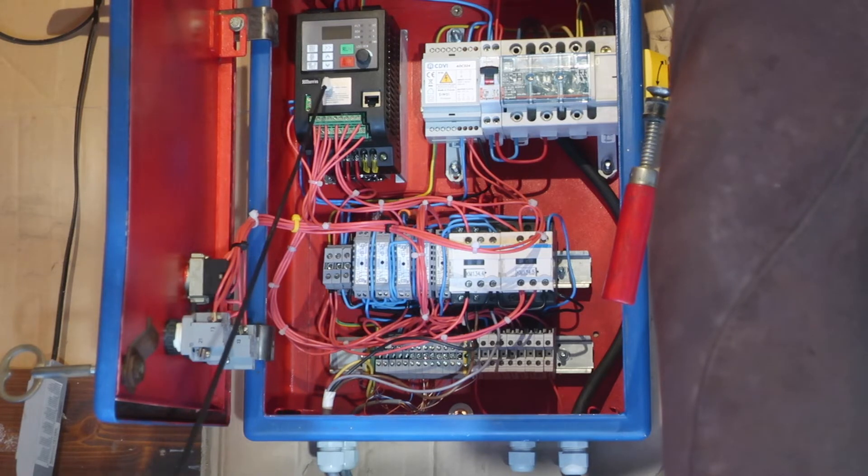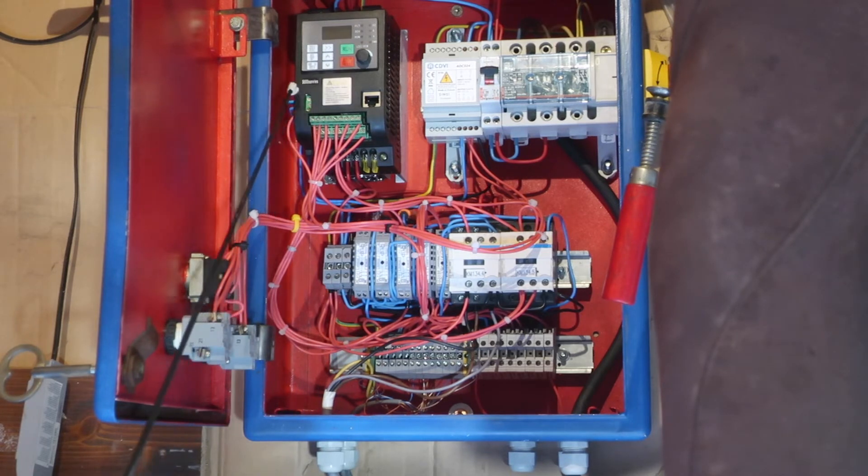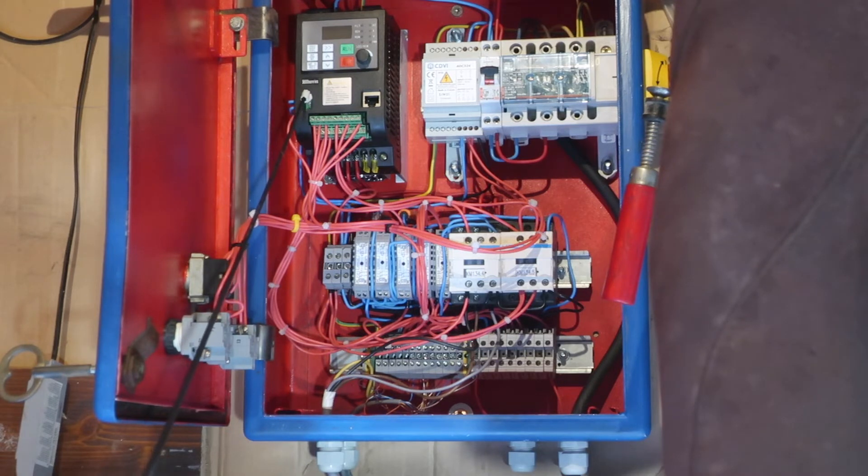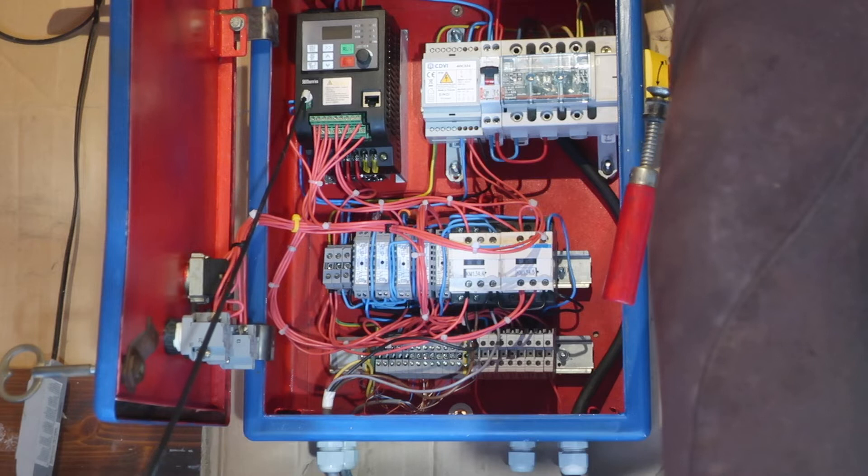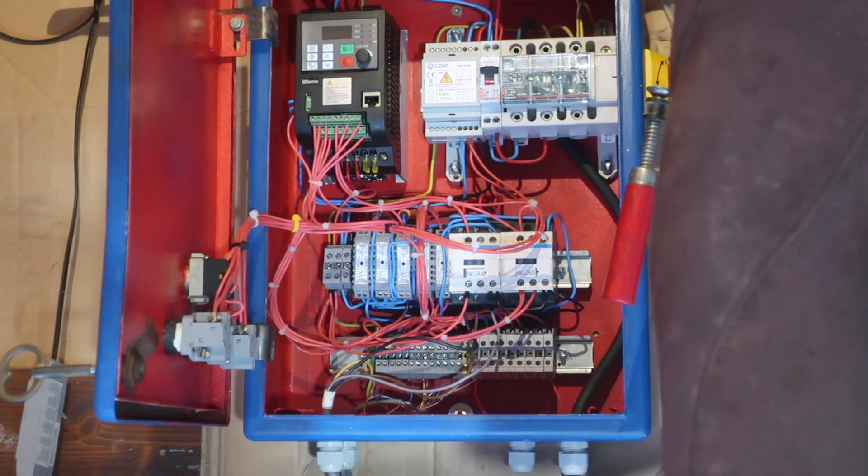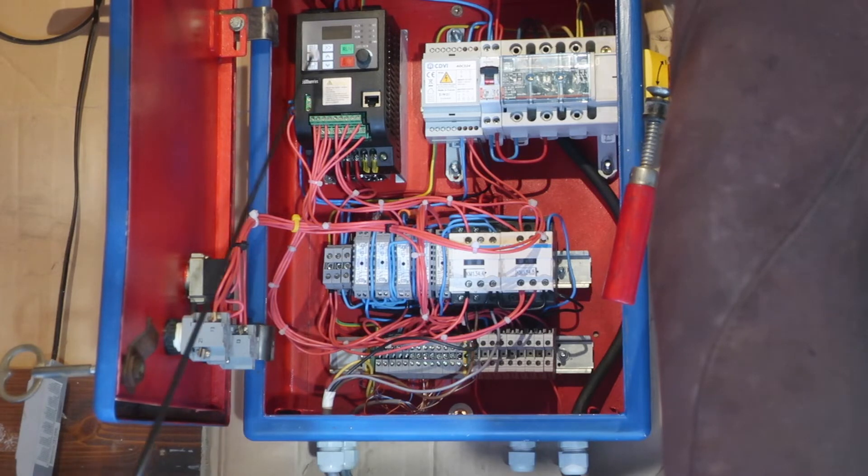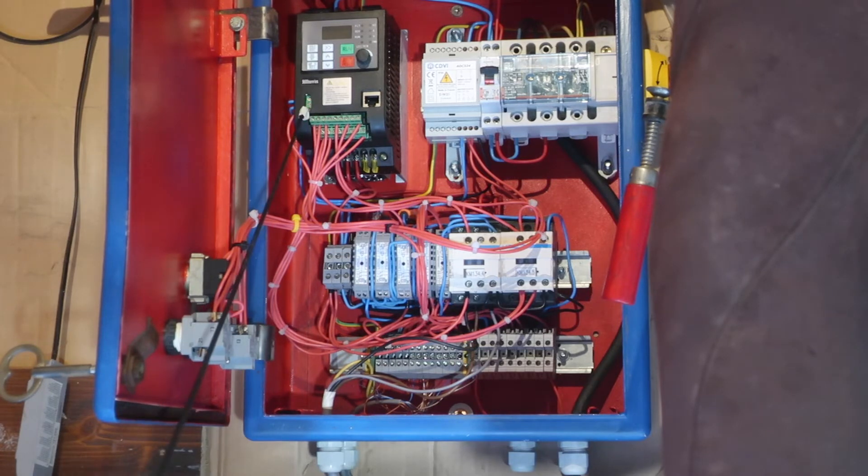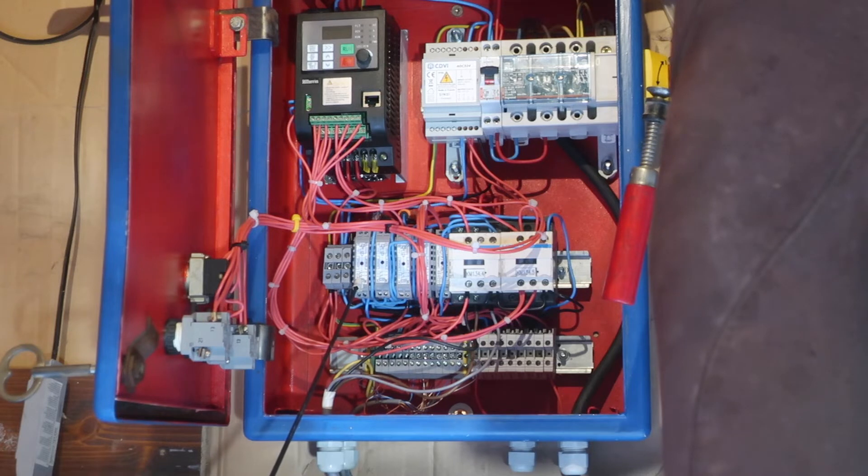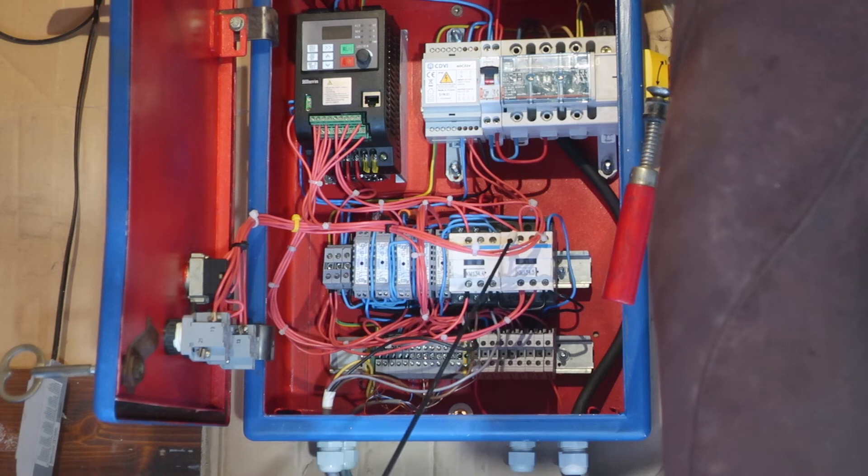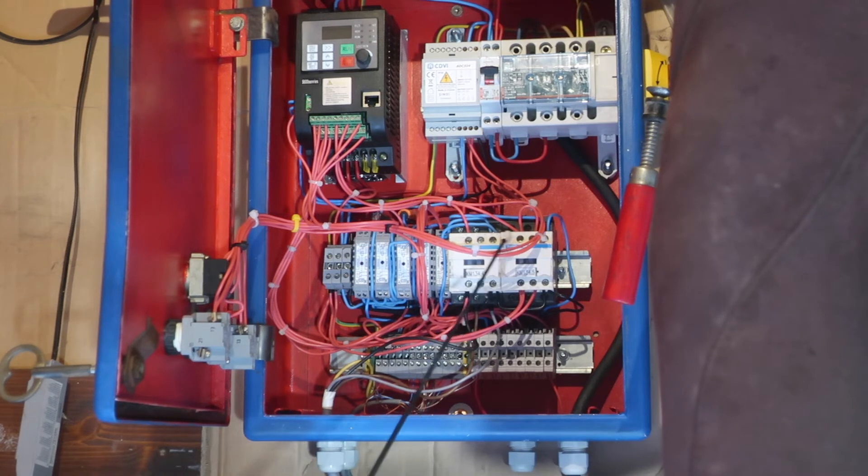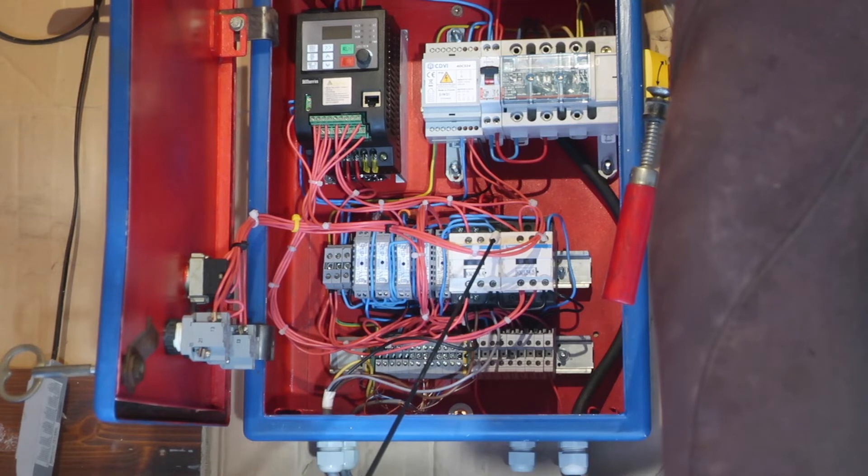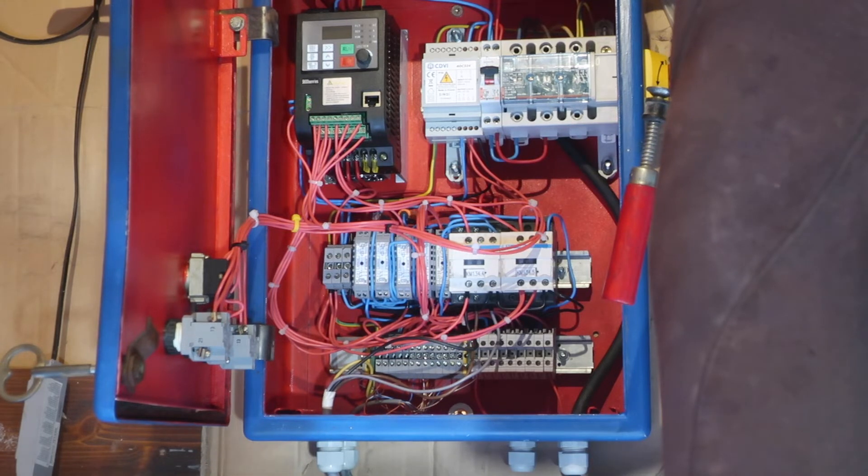Here we have the VFD. Now the VFD has some relay circuits on the side. The relay circuit on the side is used to inhibit changing the motor selection downstream of the VFD while it's running. So basically while it's running, that relay is energized, which energizes this relay. This is a double relay that inhibits a pair of contactors. This pair of contactors here for changing the machine, going from lathe to milling machine and backwards and forwards again, and then the contactors in the machines themselves for changing the speeds.